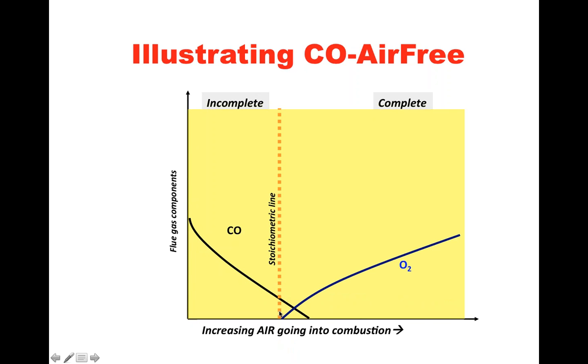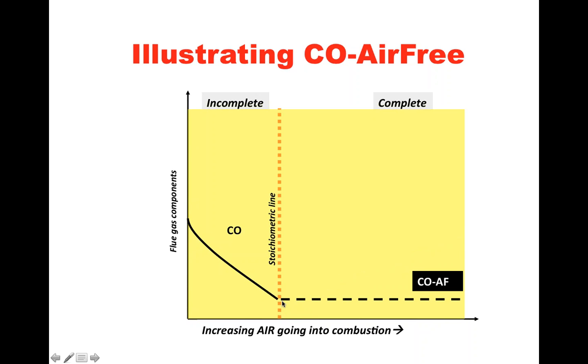Okay, I'll do that one more time. So you have CO, the raw reading from the sensor, the oxygen raw reading from the sensor, and then using an equation, the meter will come back with CO air-free, which is about the same as where the CO crossed the stoichiometric line. So this sort of gives you a viewpoint going back. No matter what the level of oxygen is, you can go back and view where carbon monoxide crossed the stoichiometric line. So it's sort of like border control here. It tells you where it crossed the line, and you don't have to know. It could be at various points of combustion or oxygen levels. So this tells you the CO air-free is the point at which you have no excess air. What was that CO level? Let's go back and calculate and look at that.